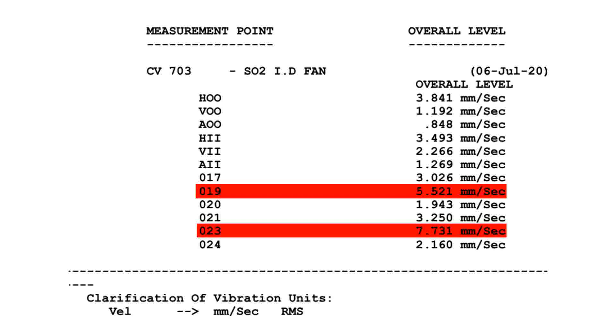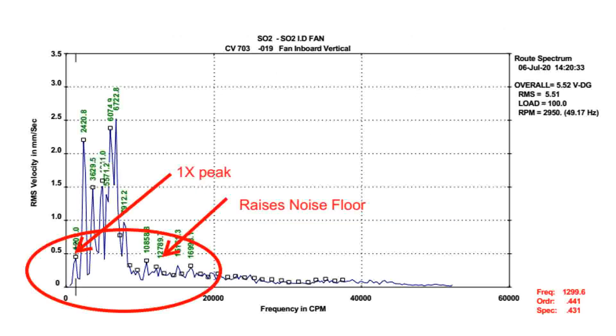We inspected the fan with vibration analysis. In this study, you can see a raised noise floor due to flow-induced vibration in the FFT spectrum.